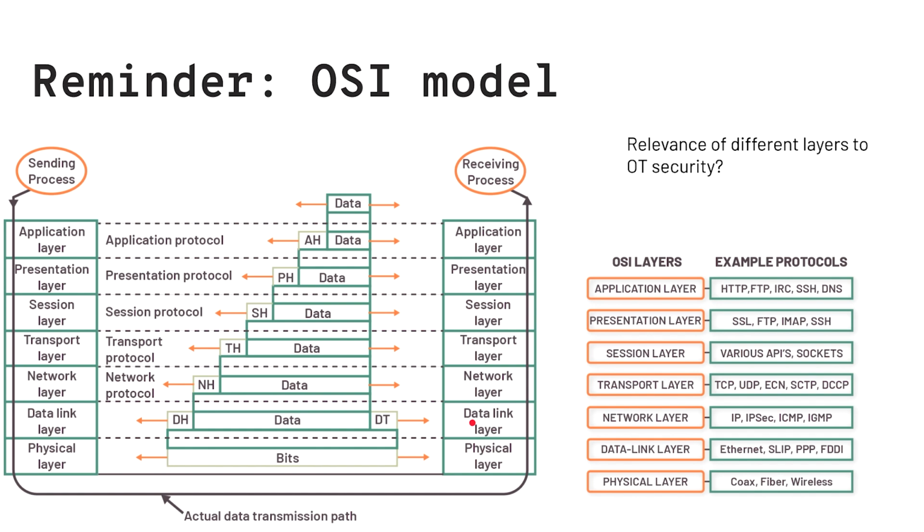Data link may be the most relevant to operational technology security. We have the industrial Ethernet we discussed before. Both the connectors have to be of a special type to withstand harsh conditions. But the Ethernet layer matters because typically when you go to the control side, you don't have TCP/IP traffic, right? You may have some IP routability nowadays, but we still have many control networks that are daisy chain or star topology with proprietary protocols connected, nowadays through industrial Ethernet. So this is one of the most important ones, and we'll see many attacks and defenses at the data link layer.